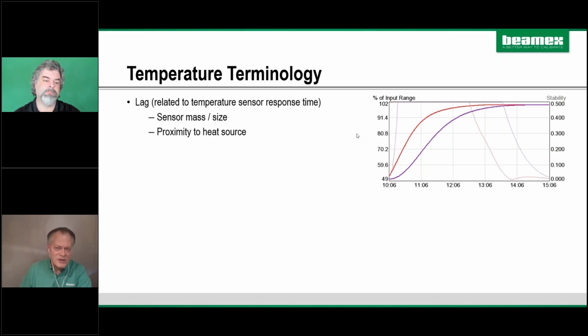And of course, how close is the sensor to the heat source? So when you're in a dry block, it's inside an insert, and it's drilled down to the bottom, but it's not as close to the insert as, say, the internal reference sensor.